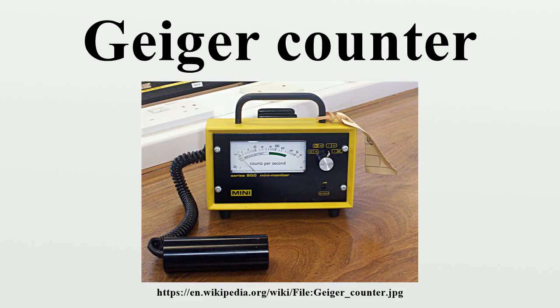The readout can be analog or digital, and increasingly, modern instruments are offering serial communications with a host computer or network. There is usually an option to produce audible clicks representing the number of ionization events detected. This is the distinctive sound normally associated with handheld or portable Geiger counters. The purpose of this is to allow the user to concentrate on manipulation of the instrument whilst retaining auditory feedback on the radiation rate.